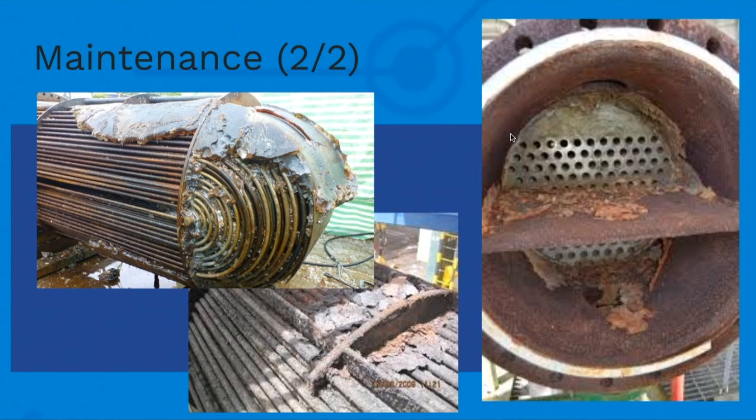Here are more examples. This is outside the tubes—inside the shell but outside the tubes. You can see the fouling material. It might be very caustic, dirty, or contain impurities that cause fouling and deposits.